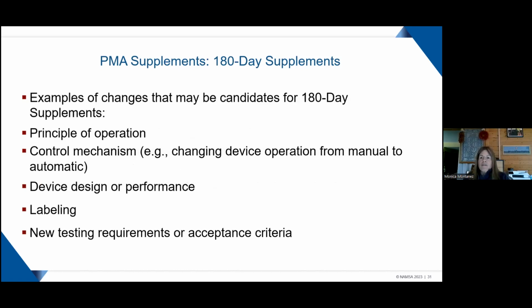Examples of changes that may be candidates for 180-day supplements are a change in your principle of operation, or control mechanism, for example changing your device from manual to automatic. Also changes in your design or performance of that particular device, and labeling, and any new testing requirements or acceptance criteria that may not have been in your previous PMA.